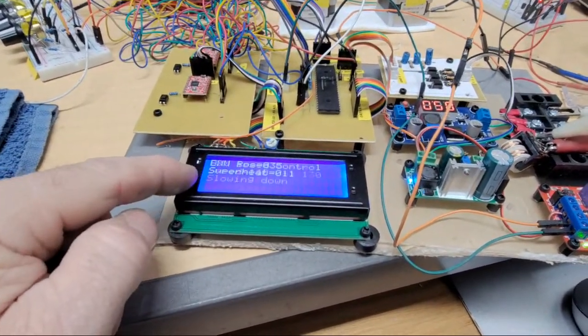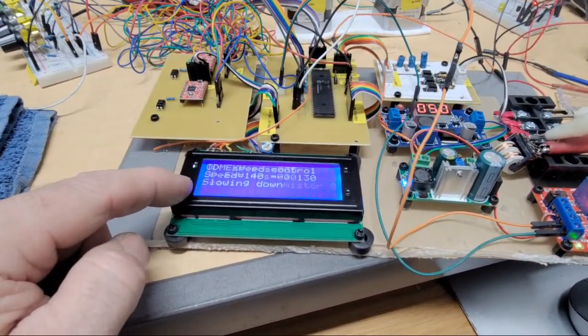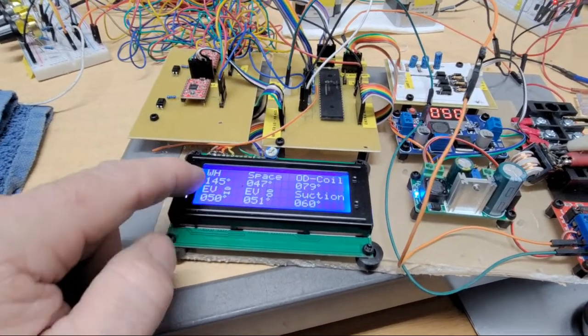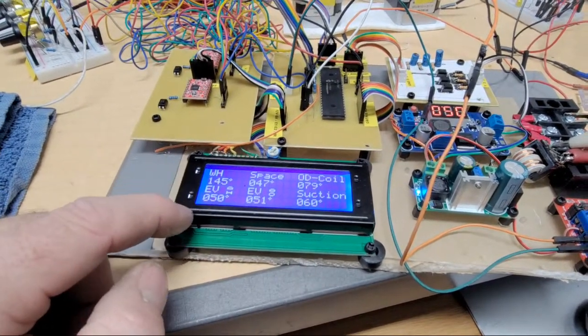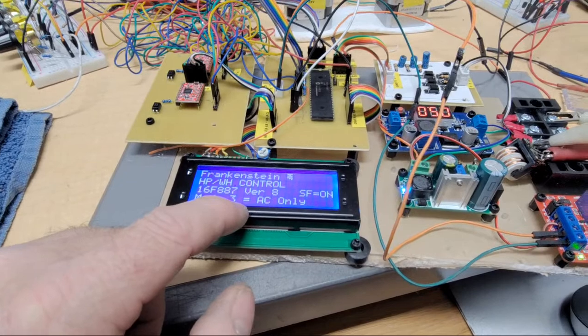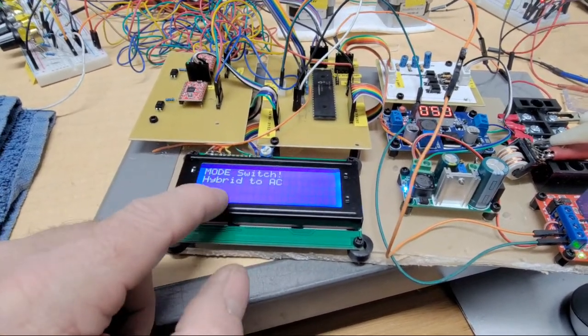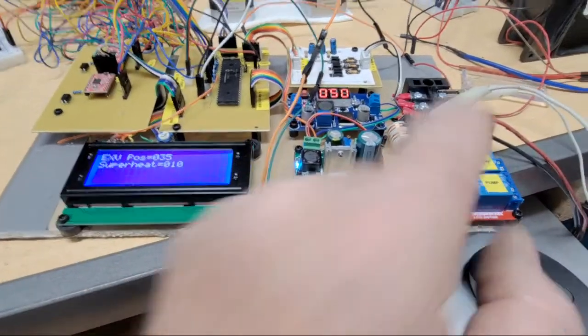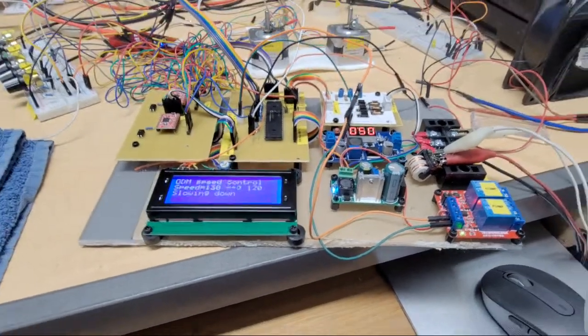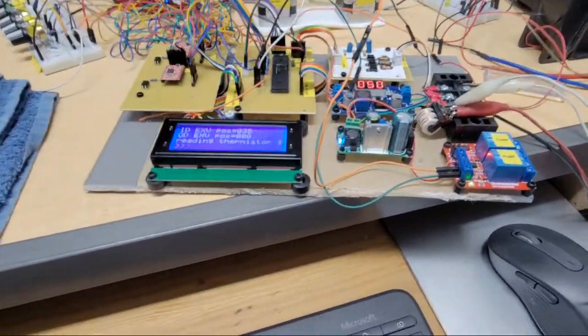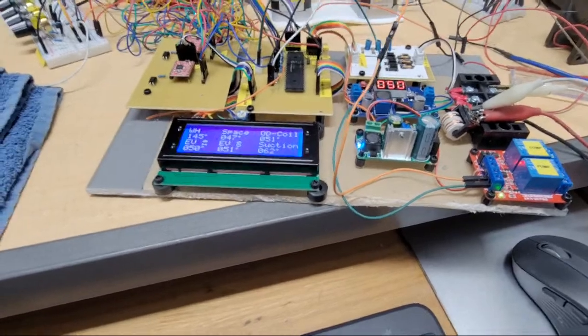There's an EXV superheat, and it will adjust if it needs to. So now you see that water heater's back up at 145, so it's going to switch modes. Mode 3, again, AC only. Now it's going to switch. The only thing it needs to do is cycle that pump for that. I have that all in the programming. If it switched, the EXV or something would be totally different.